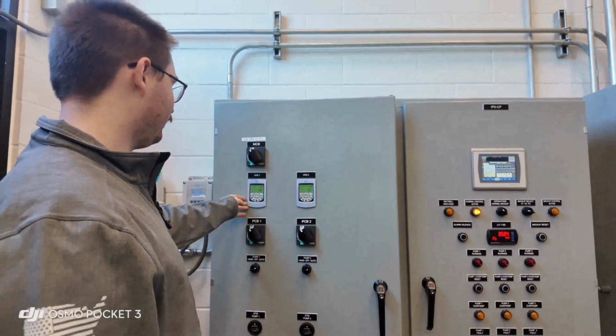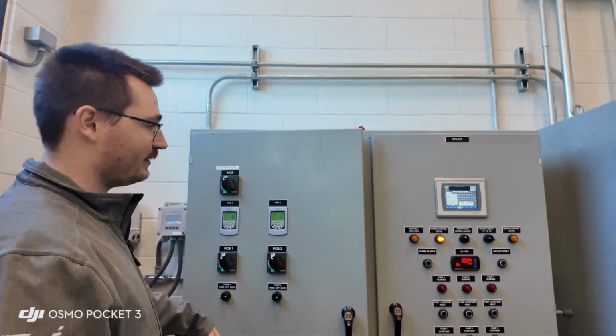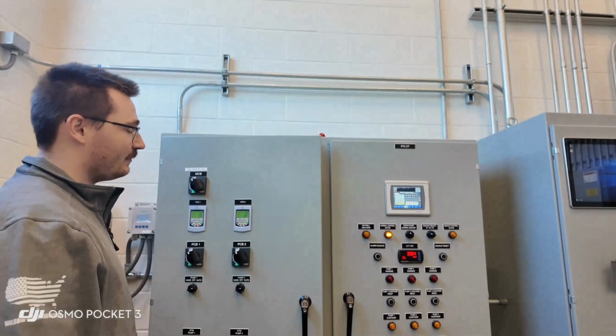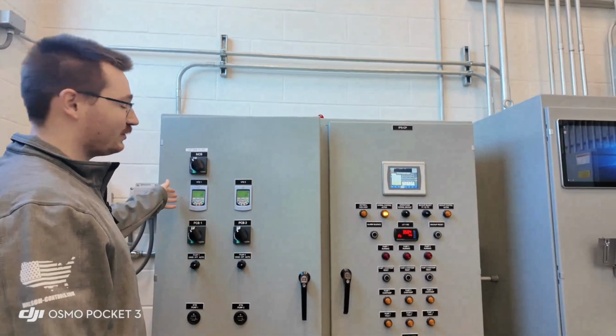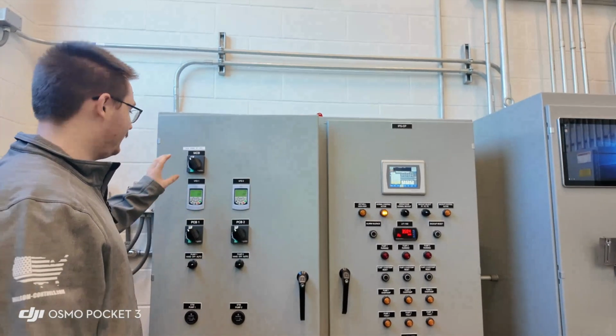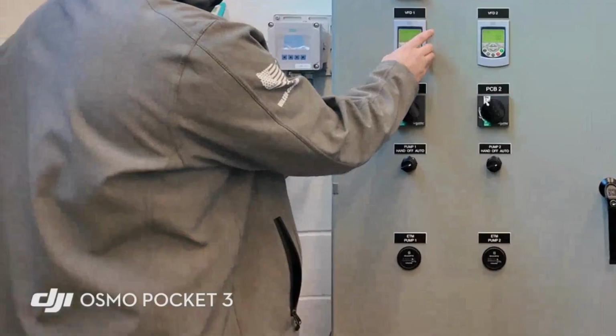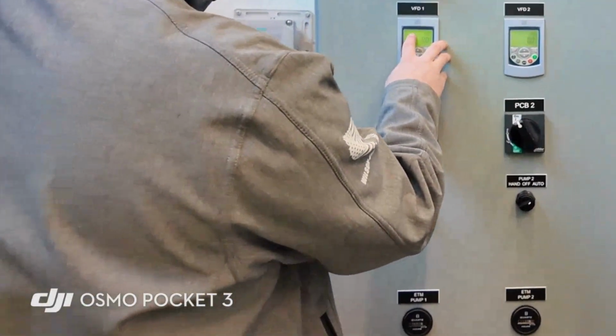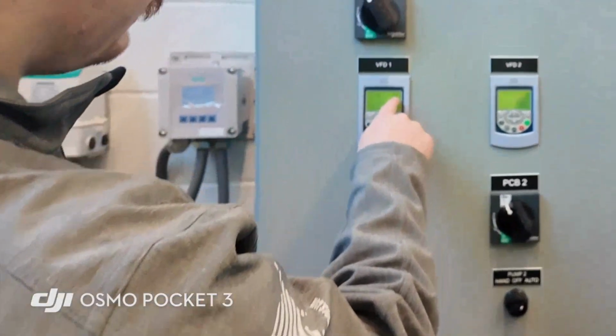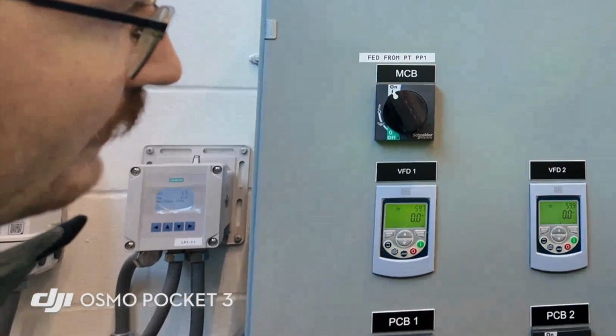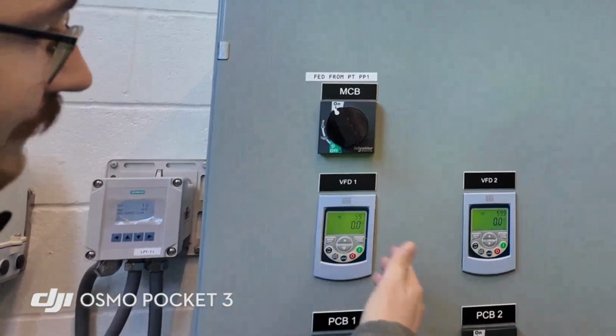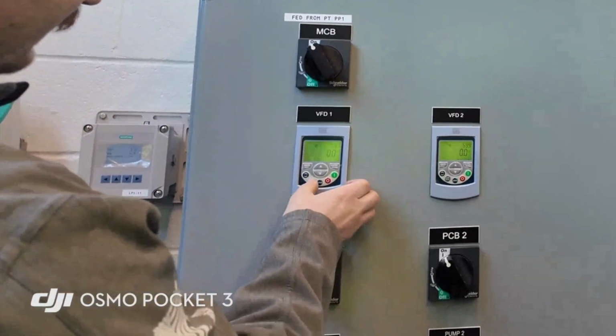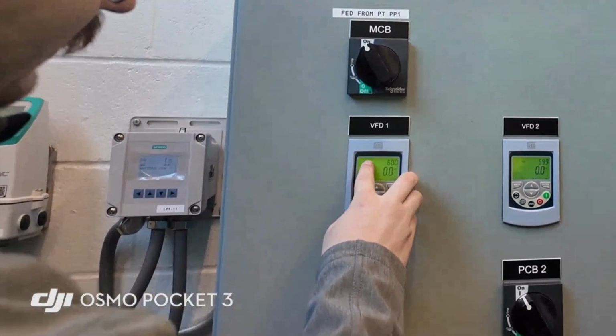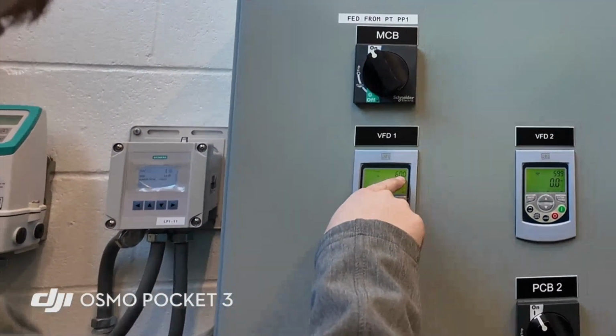This has full local control right on it, just in case the HOAs or the PLC go out. You can actually control the drives manually from this HMI. When you start the panel, it's going to be in remote, and that means it's going to be looking for a remote signal right here. So this way up here is currently what my PLC is going to run at if it's told to start. If I hit this local remote, it's going to go up here and go to local, and then it's going to ask what you want to run it at.